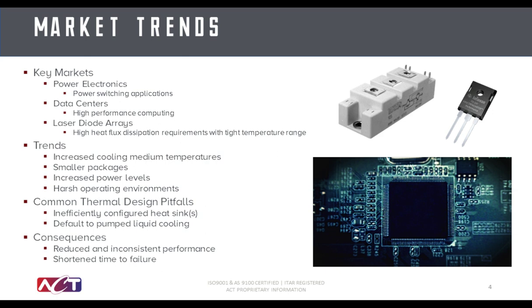Some key markets that can benefit from pump two-phase cooling technology are power electronics like IGBTs and other semiconductor-based components, some data center applications where they have particularly high-performance computing and high-powered chips, and also laser diode arrays for applications where high-powered lasers are being used for industrial processes or other applications. Trends in the market, specifically in data center applications, include increased cooling medium temperatures, the need to operate the data centers at higher temperatures for better energy efficiency, smaller packages in all of the key markets, including data centers and power electronics, trying to get more power per unit area, and obviously trying to drive the components harder with higher power outputs. All of these things result in larger thermal problems that need to be resolved.